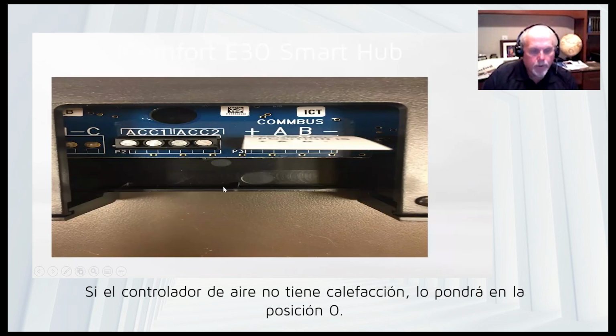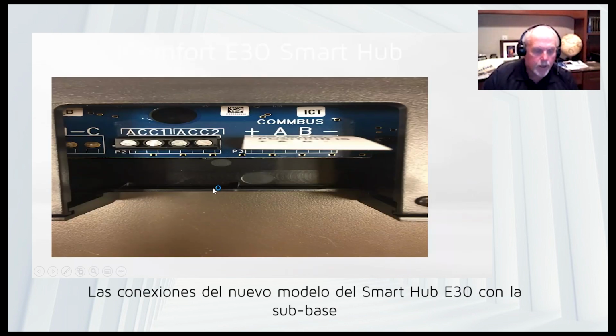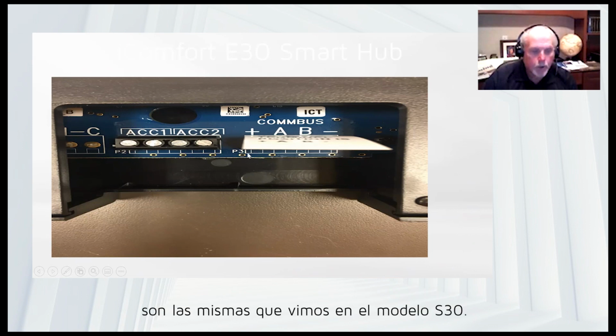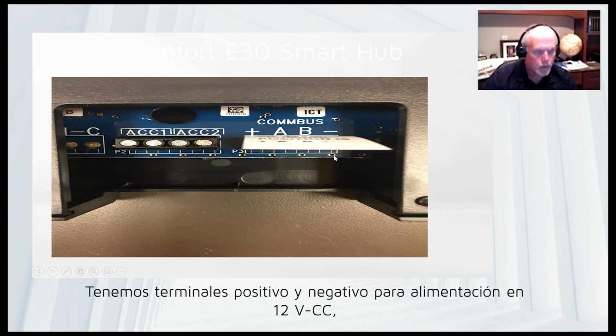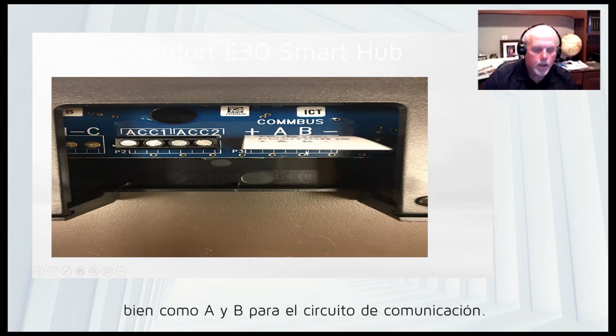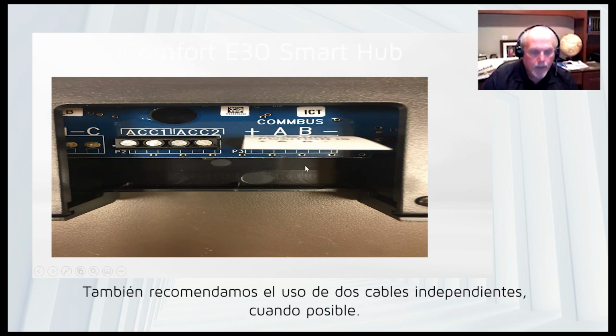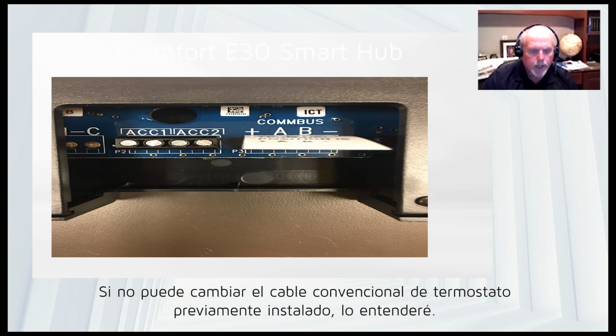Okay, so with the new E30 Smart Hub, what connects to the display subbase is the same as the S30. You have a plus, you have a minus, that is 12 volts DC. A and B is a communicating circuit up to the display subbase. And we recommend 2 cables if you can do that. That cable is going to be the hardest one to pull. If you can't change it, okay, I understand.